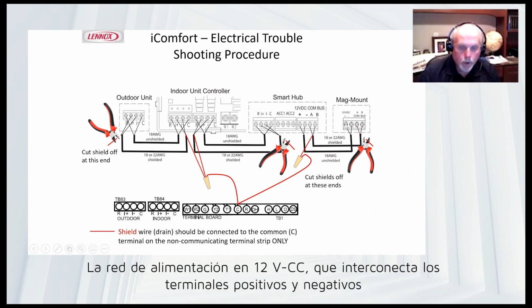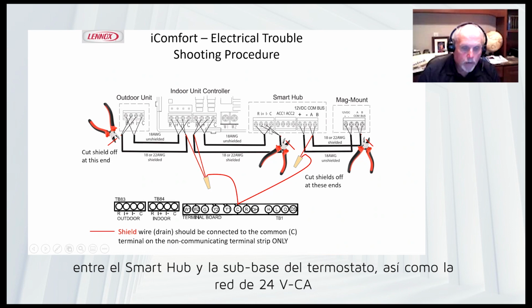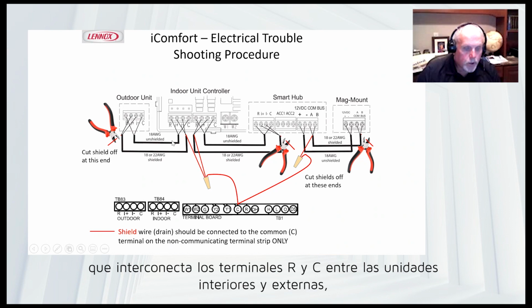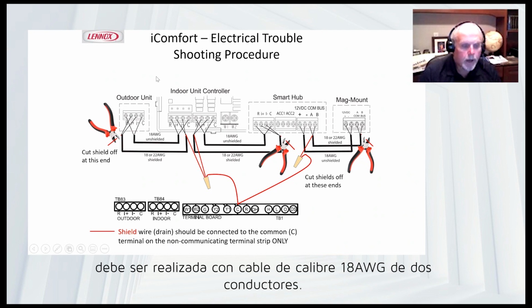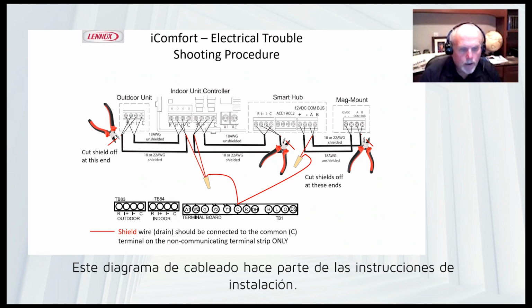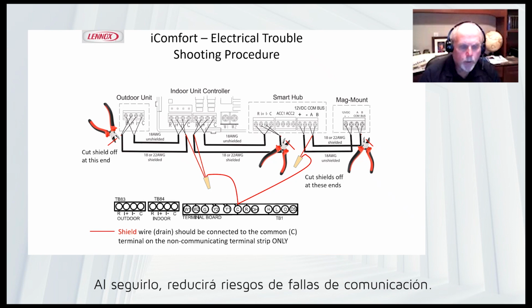The power supply, which is your plus and minus, which is 12 volts on this side, and from the Smart Hub to the indoor unit, R and C, and then from R and C from the indoor unit to the outdoor unit. That is all your power supply, and that is recommended to run in two conductor regular 18-2 thermostat wire. So two separate cables of two conductor wire is recommended here. This wiring diagram is in the installation instruction, and if you follow this, it will greatly reduce the problem of communication errors. So following this wiring in the installation instruction will certainly help cut down on those things.